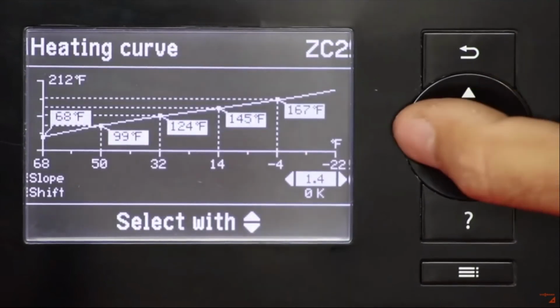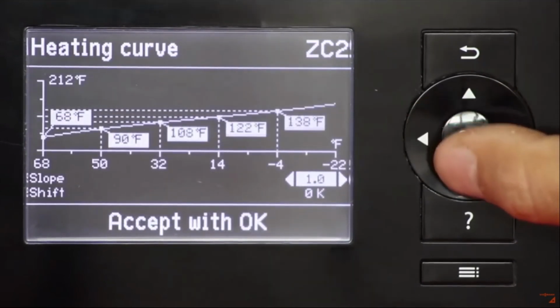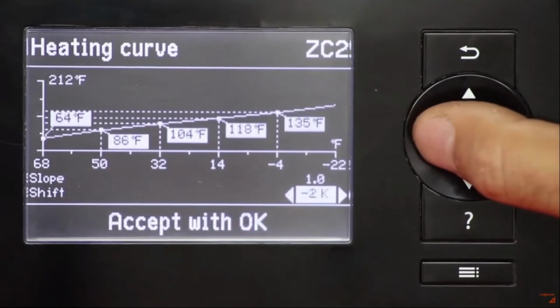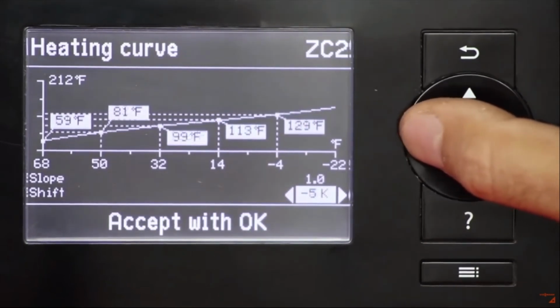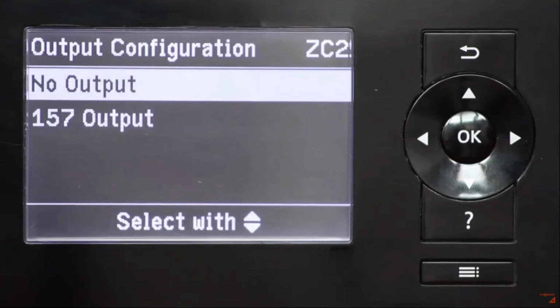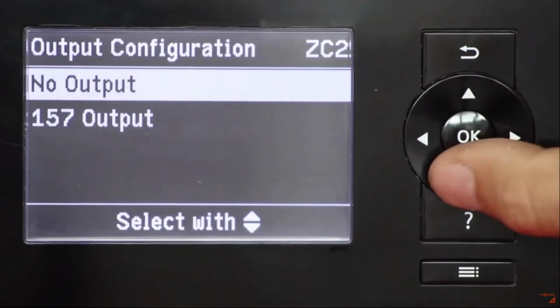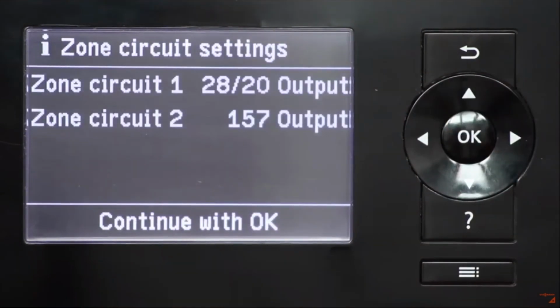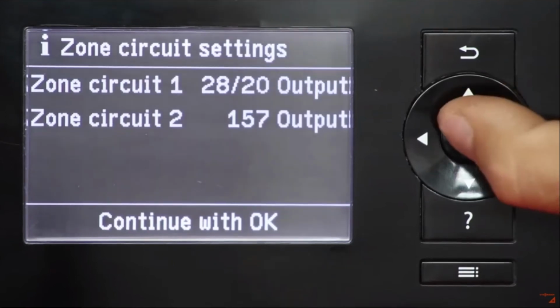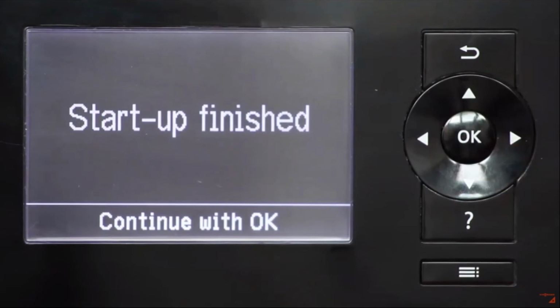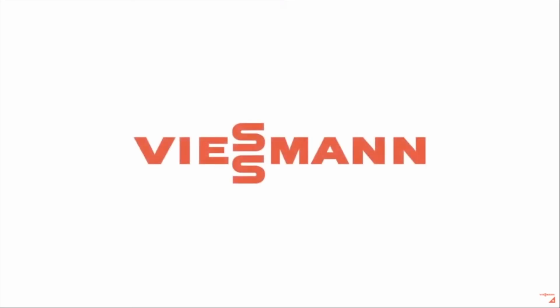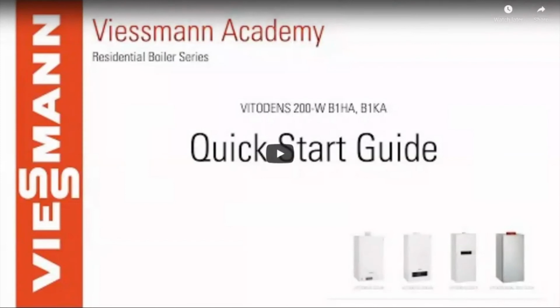Under the heating curve screen, make the necessary adjustments to the slope and shift to achieve the desired heating curve. Next, you can select the desired pump output for the zone circuit. The zone circuit settings screen summarizes your selections. Continue with OK, and the startup is now complete. So you can see it's pretty quick and easy to start up this boiler.